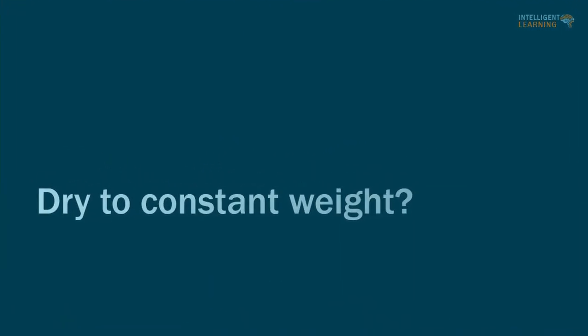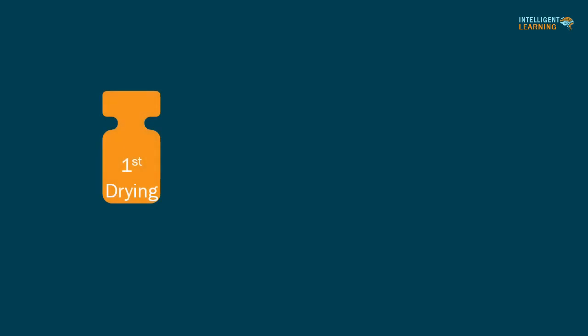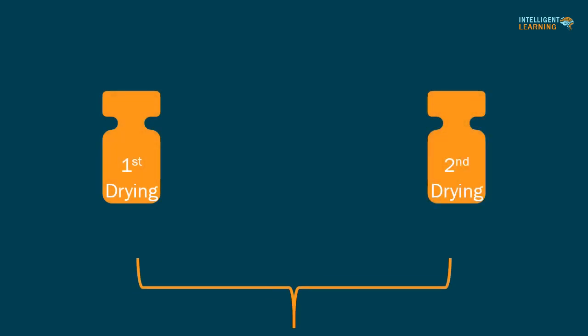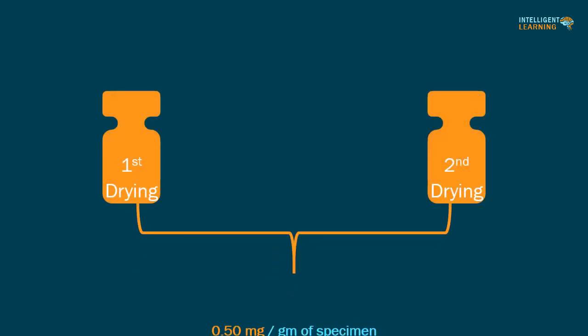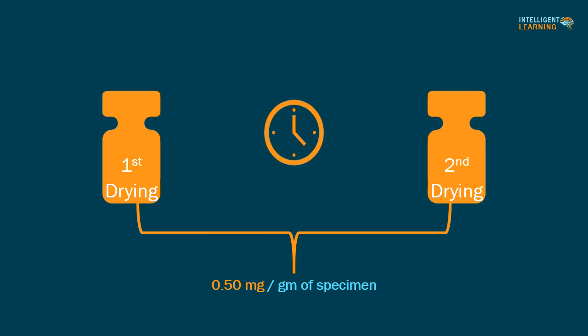Meaning of dry to constant weight: when 'dry to constant weight' is specified in a method of analysis, drying shall be continued until two consecutive weighings do not differ by more than 0.50 milligrams per gram of specimen, where the second weighing follows an additional hour of drying.